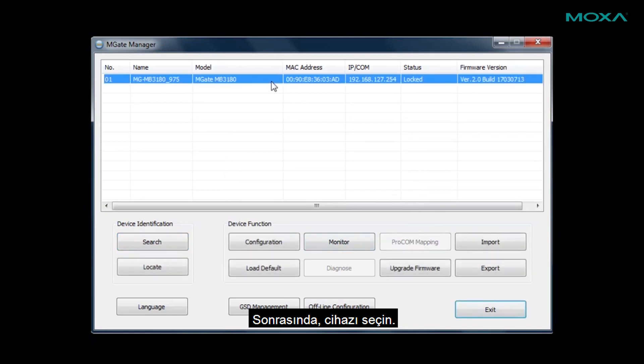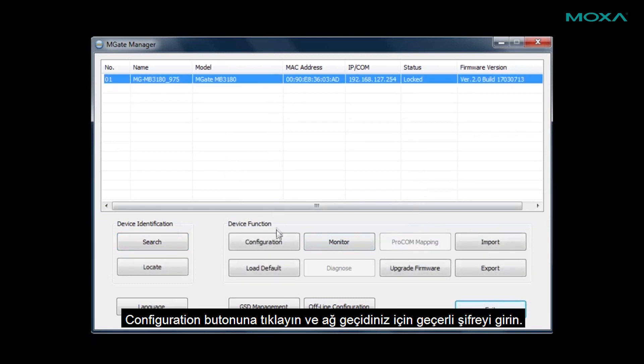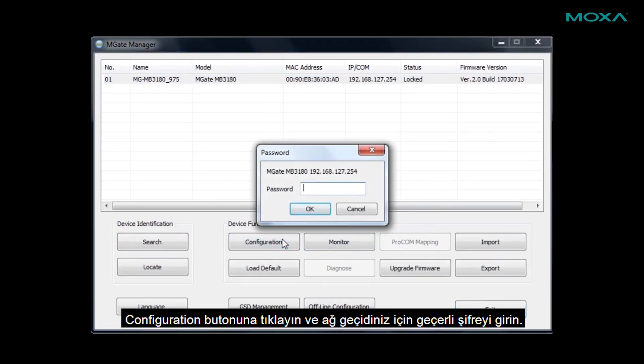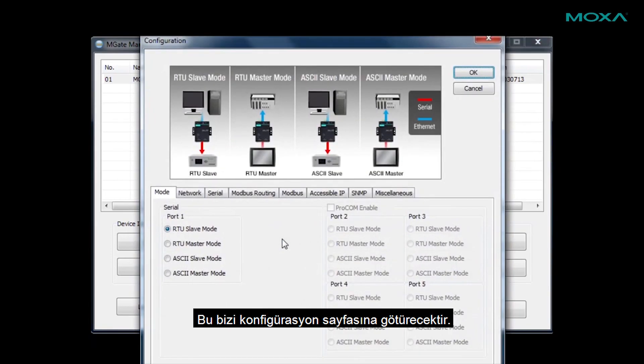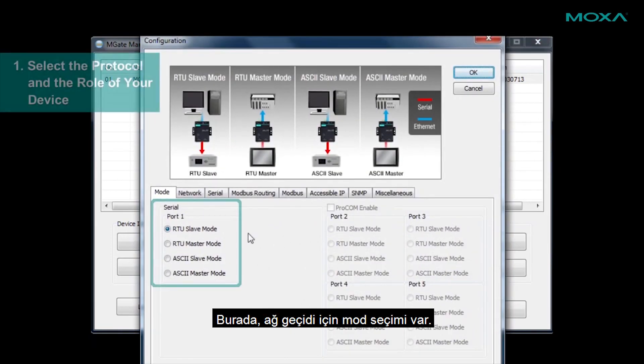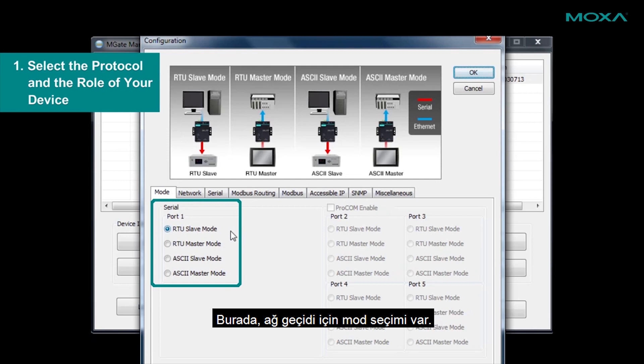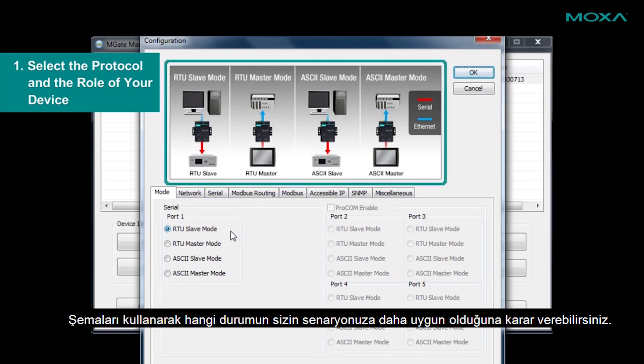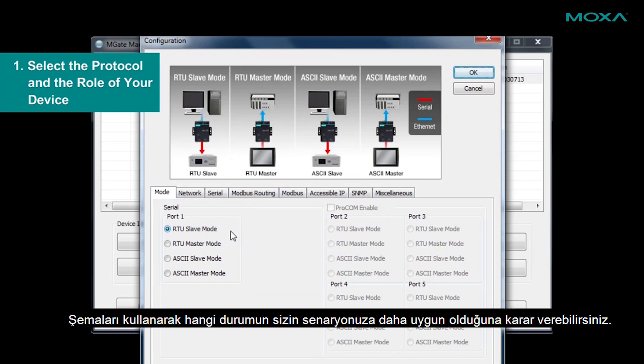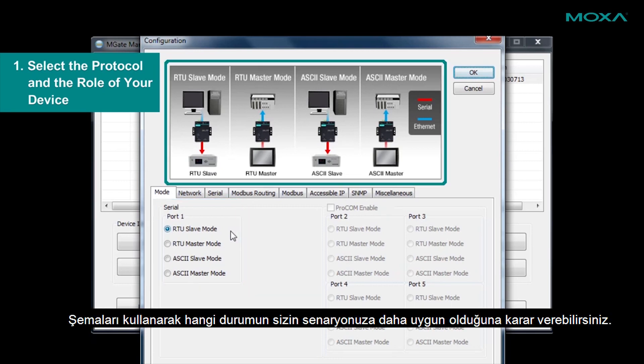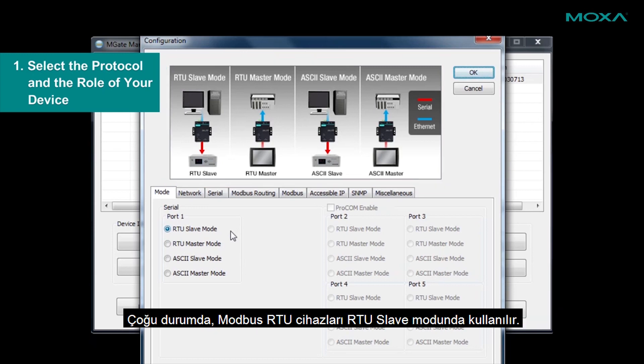Next, select a device, click the Configuration button, and enter the password for your gateway. This will take us to the Configuration page. Here, we have mode selection for your gateway. You can use the diagrams to determine which mode best fits your scenario. In most cases, Modbus RTU devices will use RTU Slave mode.